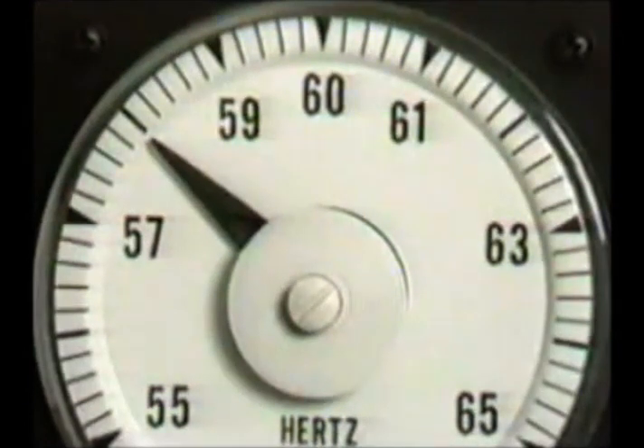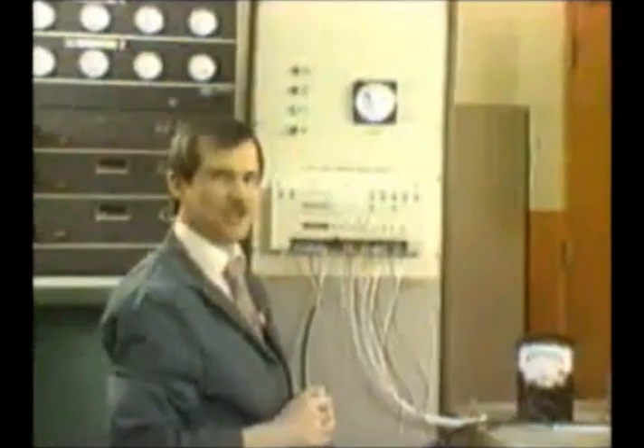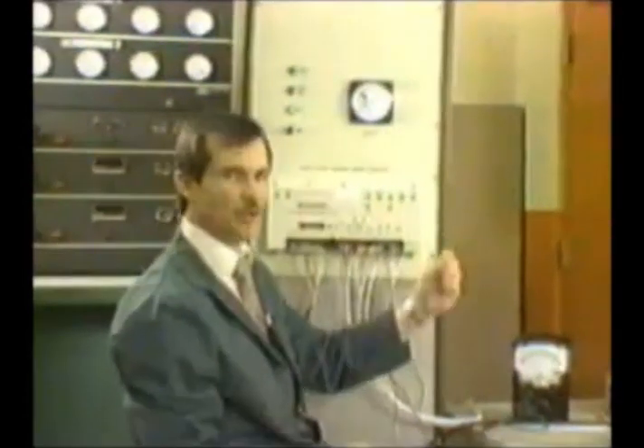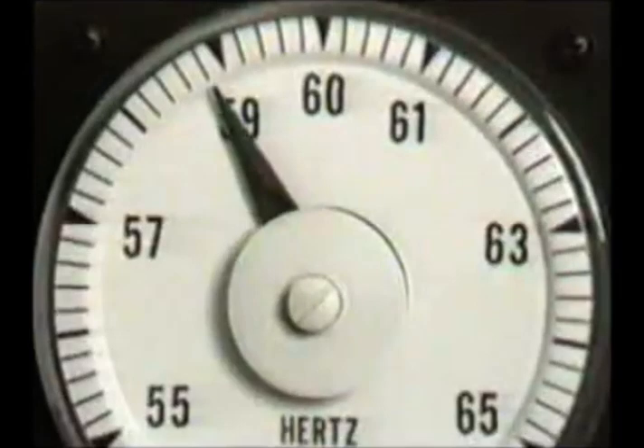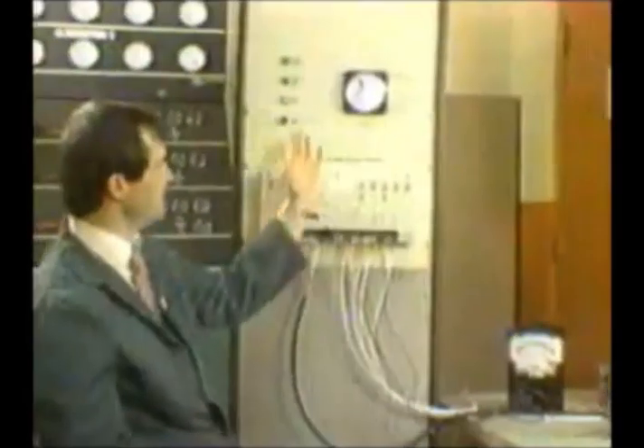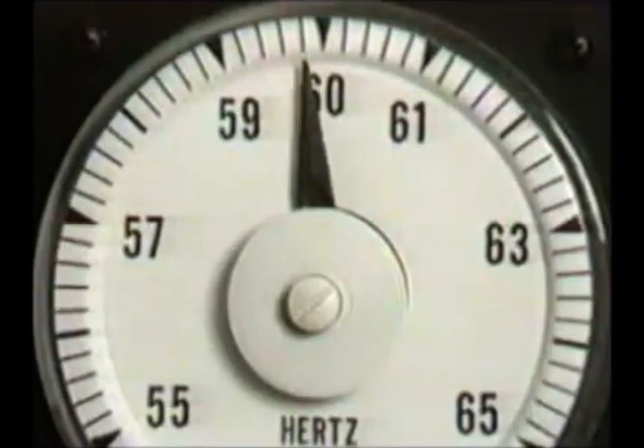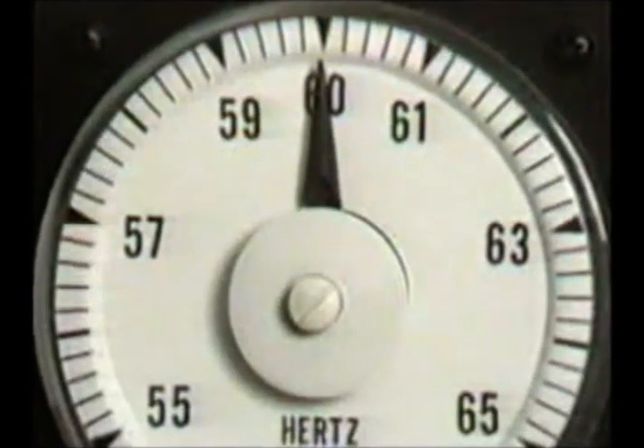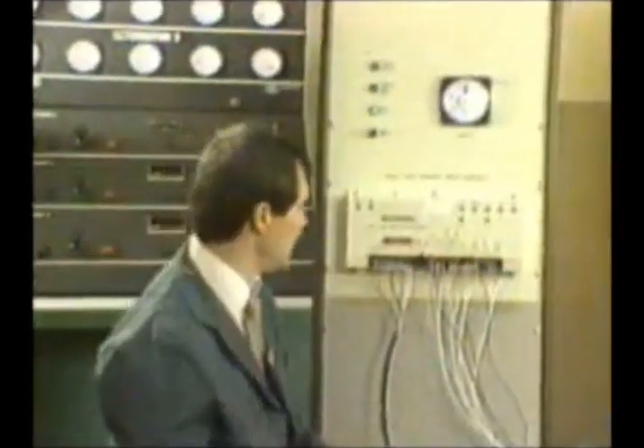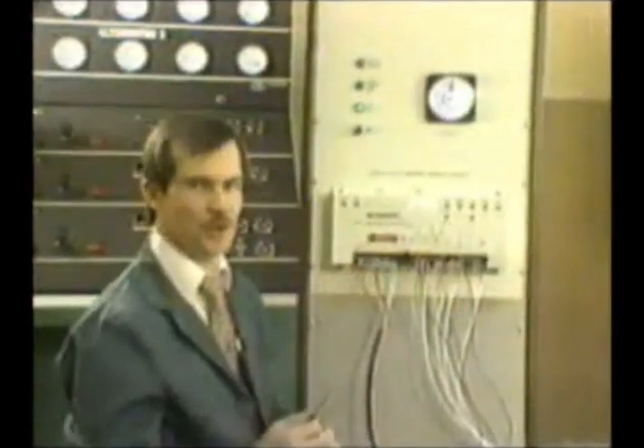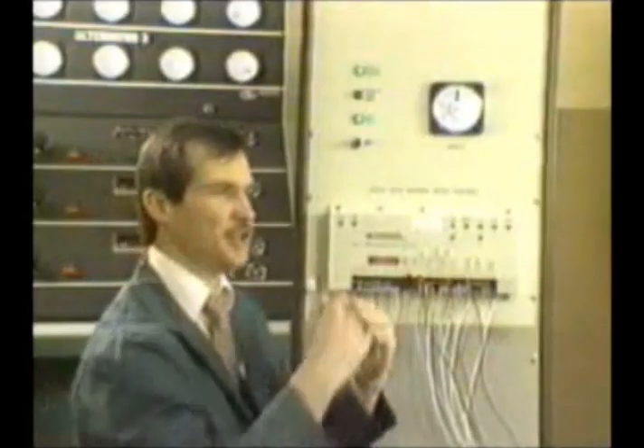So I take a load off, my load gain voltage comes down, my speed will go back up. I'll take some more load off, load gain voltage decreases, the speed increases. Take my last 2 loads off, load gain voltage is down to 0, and we're running at 60 Hertz. So that's droop. We're set up for a 5% droop right now. Now let me go ahead and close my circuit breaker auxiliary contact. This will be like you just closed to a load bus. You're going parallel with another unit.